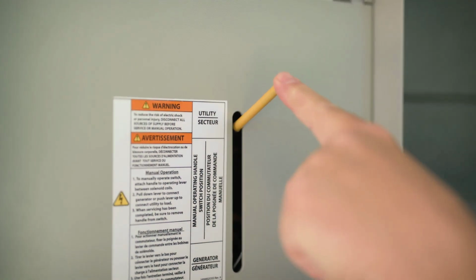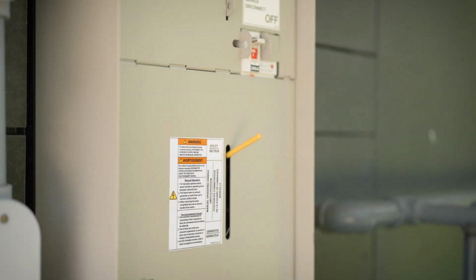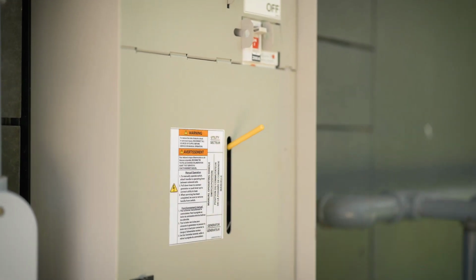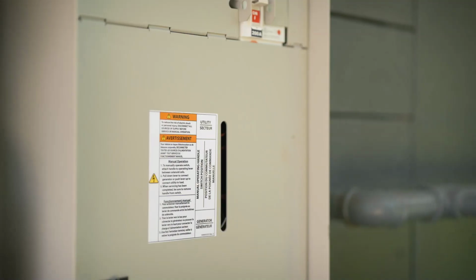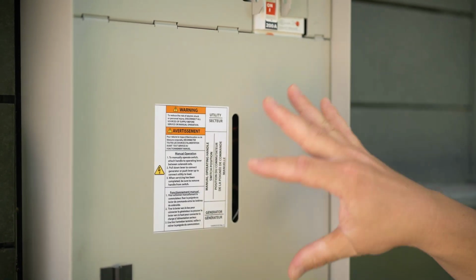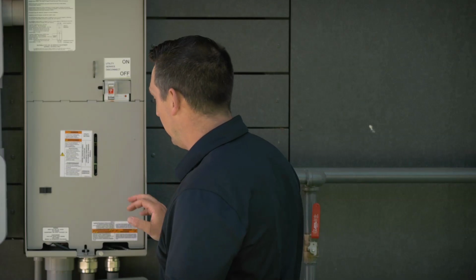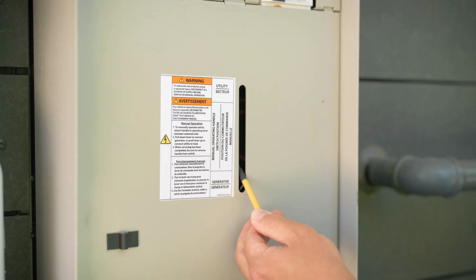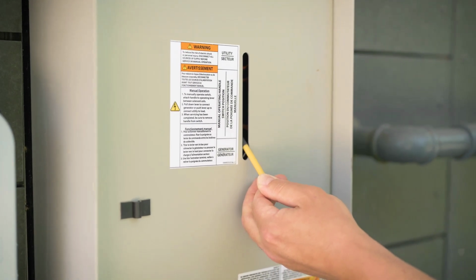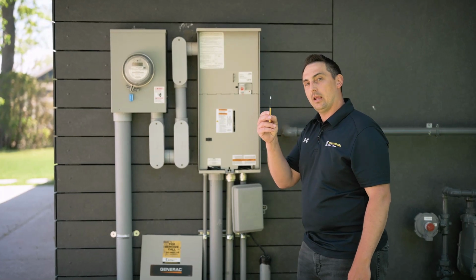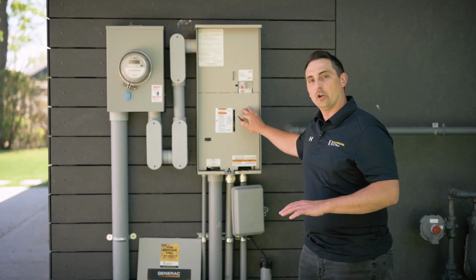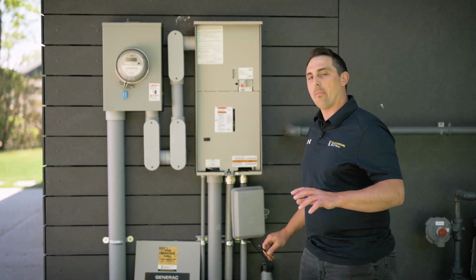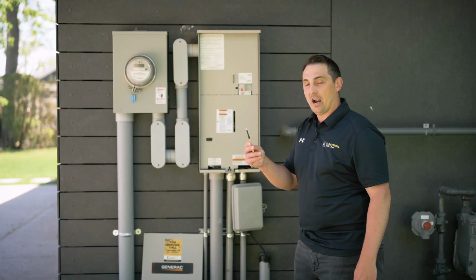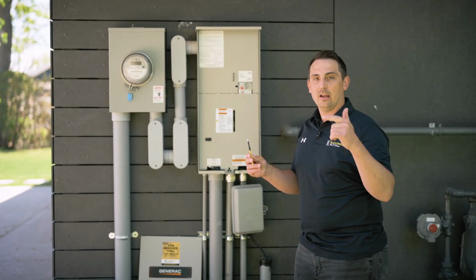Inside this slotted groove, you'll see there's a hole where the tool gets inserted. You can see in its current position, this home is operating from the utility. If the home was operating off the generator and everything was working properly with the transfer switch, the position for this tool would be down here. This tool should be used and the mechanism operated under a no load situation, meaning all the power in the home is off, and I don't recommend homeowners use it by themselves. If you're having issues, you call our 24/7 line and we're there to help.